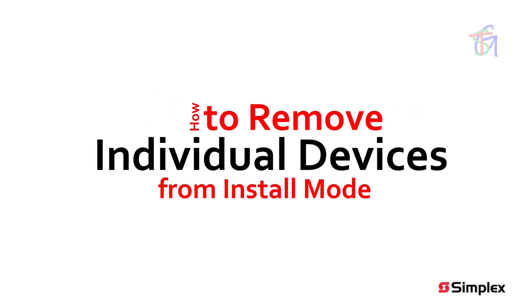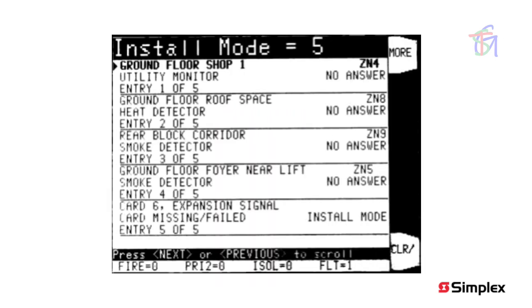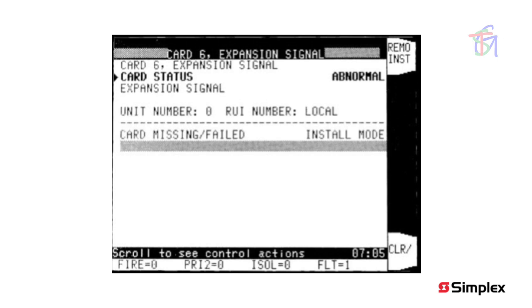If you are logged in at level 3, you can remove individual devices from the install mode list. Display the install mode list, move the highlight to the device you wish to remove, and press the more soft key to see more info. Move the highlight to the card status or device status line, and a remove soft key option will appear. Pressing the remove soft key will remove this device from the install mode list. If the device is still in fault, the system fault count will increase and the fault indicator will flash for a new fault.